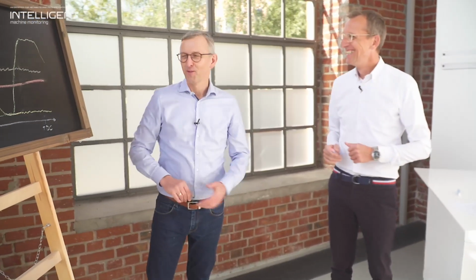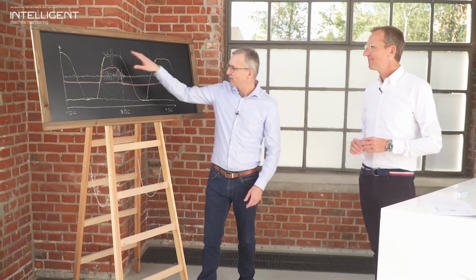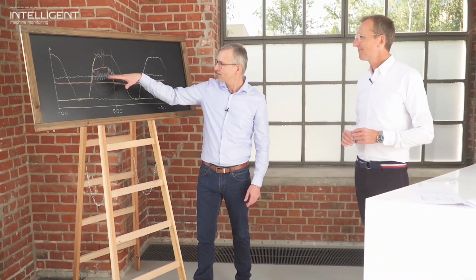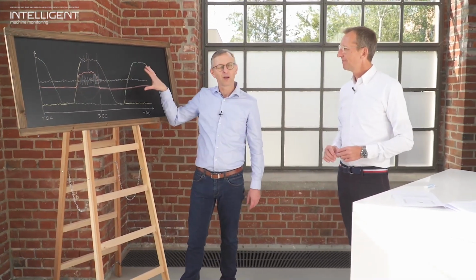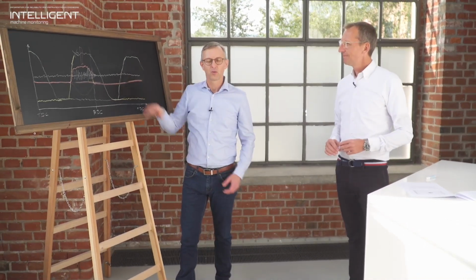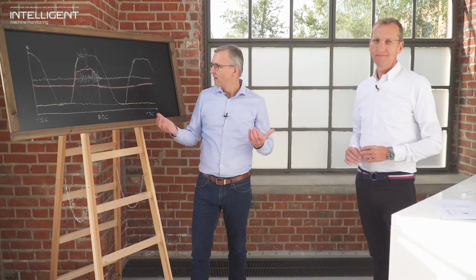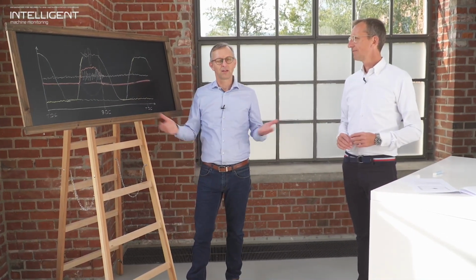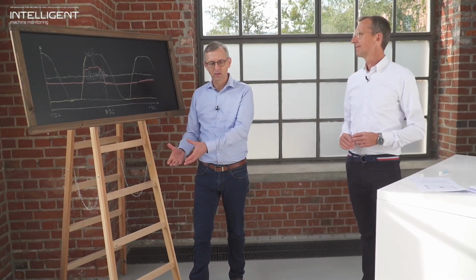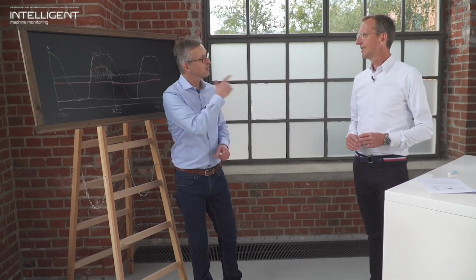Thanks again. Maybe one thing. Yes. There's one more thing. We should not forget, and I actually forgot to explain this before, but I think it's important. What you've seen, that I changed two of the parameters. I changed the vibration and also the piston rod movement, but you saw I did not change anything on our PV diagram. And this is surprising for many people, that the PV diagram is not affected by small portions of liquids going through, and the reason is that the gas pressure remains on the same level. There's no influence just because there's fluids instead of gas. Still, the end pressure and the movement of the pressure remains the same. I just wanted to add that, sorry.